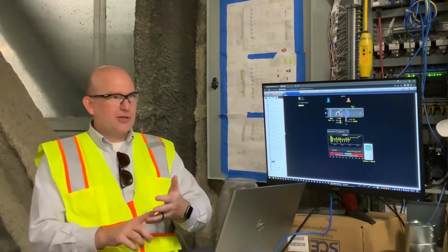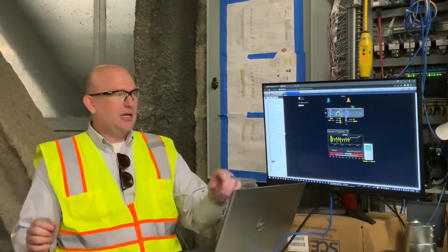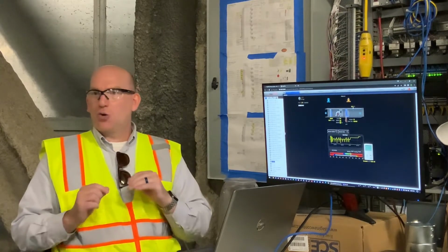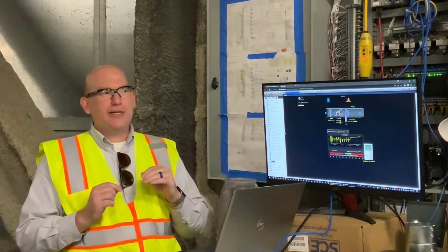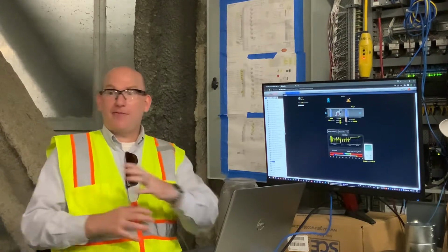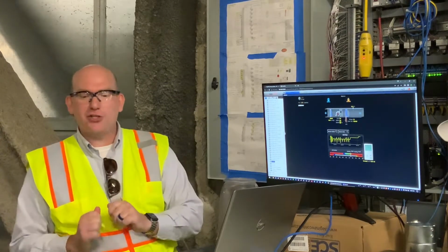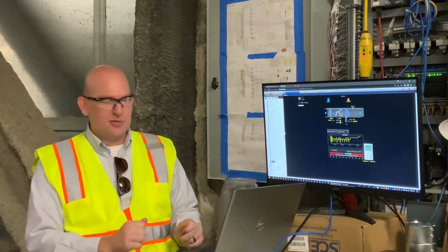There are no VAVs or anything like that. There's just chilled beams, and so those same fire smoke dampers modulate. And so we target a specific, just like a giant VAV for the entire floor, the fire smoke damper modulates to control how much air goes into the floor and how much air comes out.